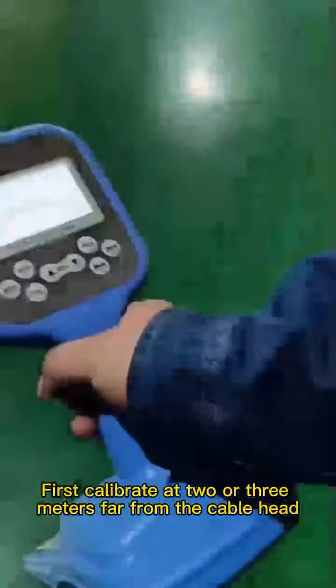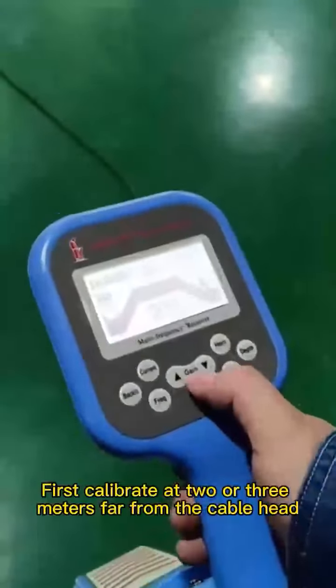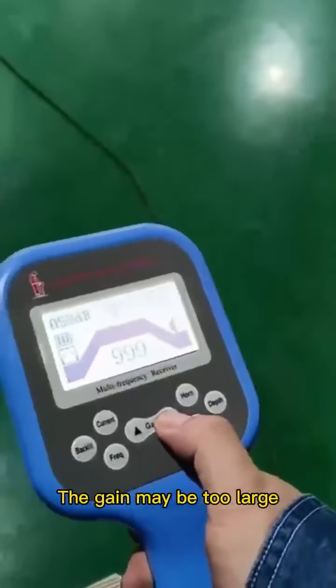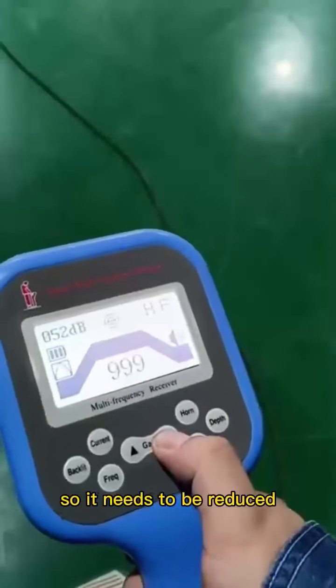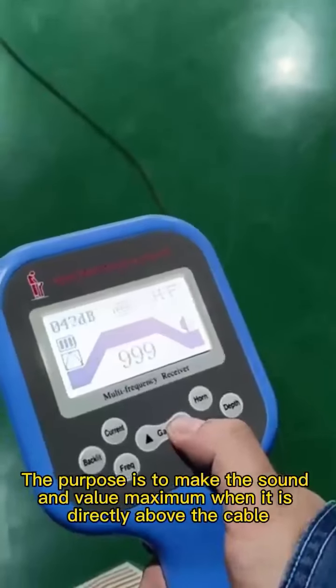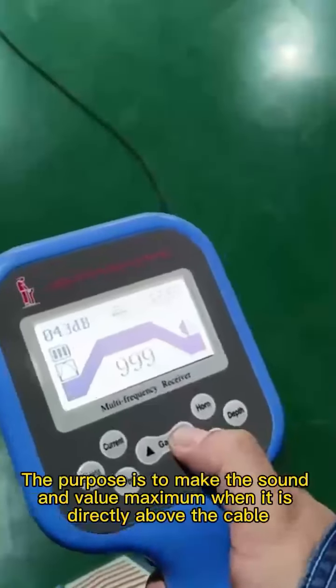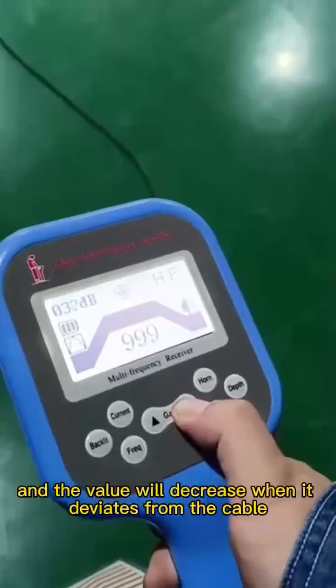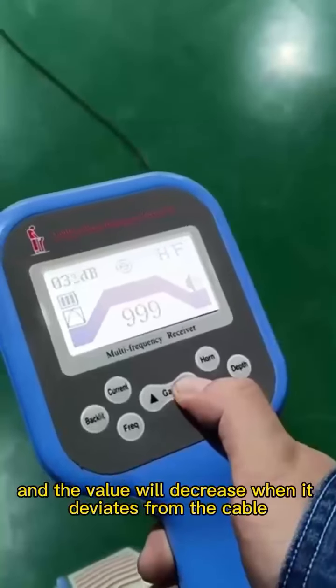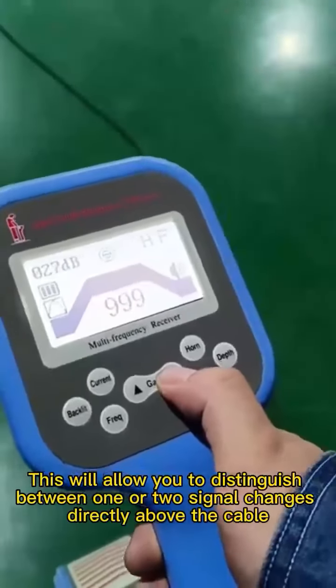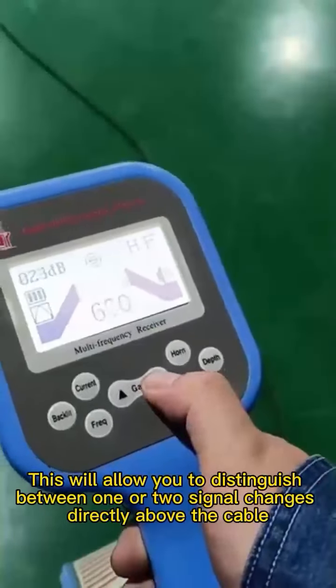First, calibrate at 2 or 3 meters far from the cable head. The gain may be too large, so it needs to be reduced. The purpose is to make the sound and value maximum when it is directly above the cable, and the value will decrease when it deviates from the cable. This will allow you to distinguish between 1 or 2 signal changes directly above the cable.